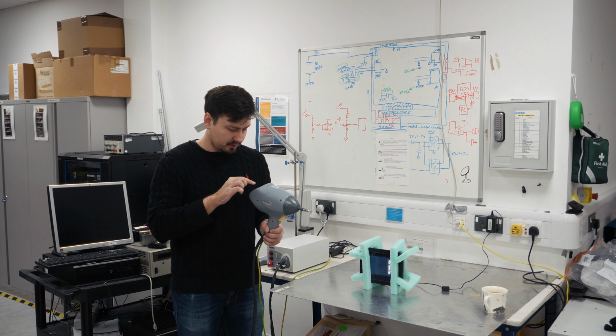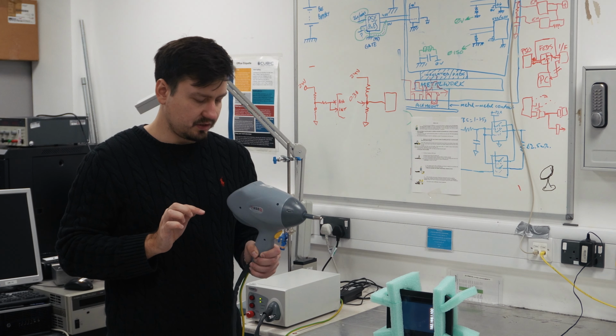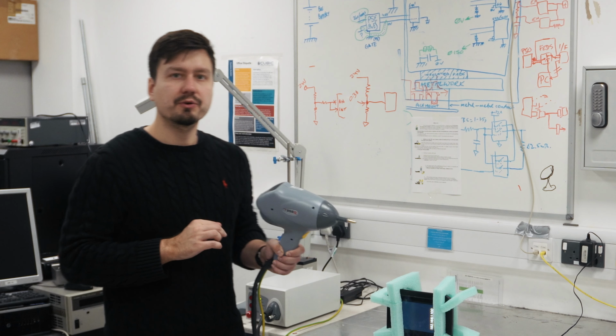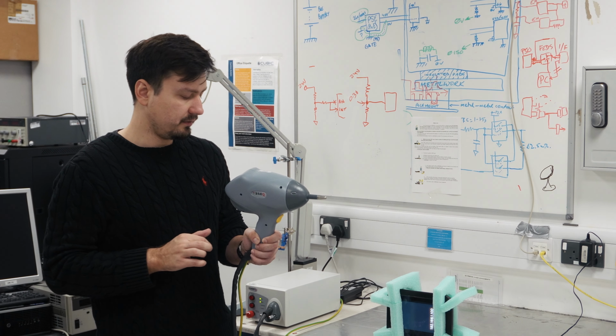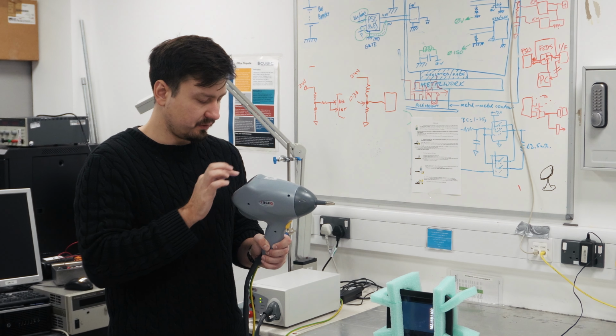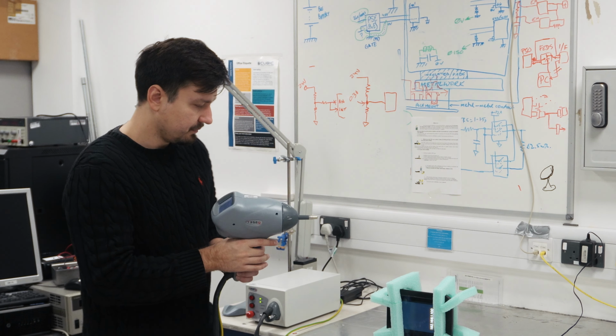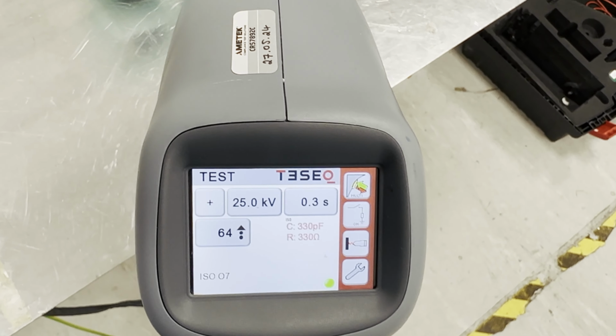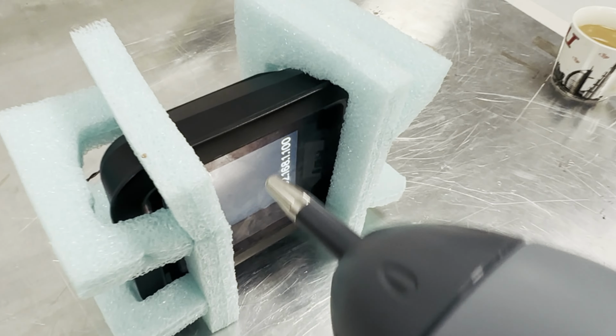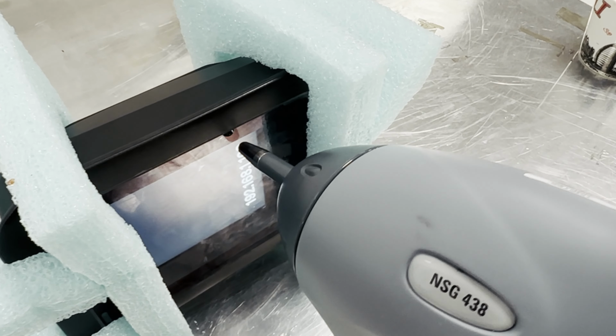So, okay, I'm selecting ISO, I'm selecting the same probes, and this time I go to 25. This is actually the maximum test level. You cannot select more than 25 kilovolt. We're going to start with positive polarity and let's see what happens. The settings are more or less the same for the air discharge, and basically we're just going across the display.